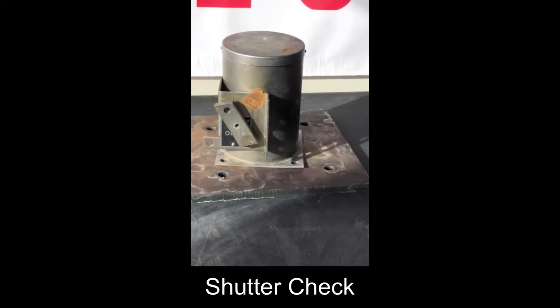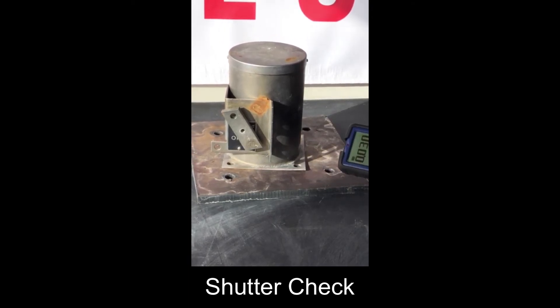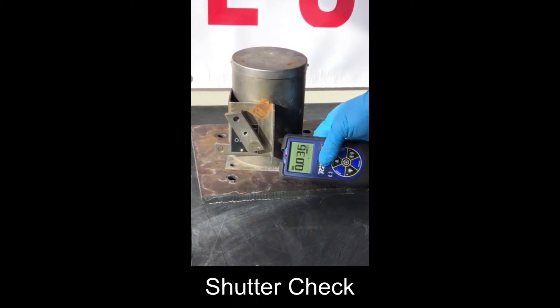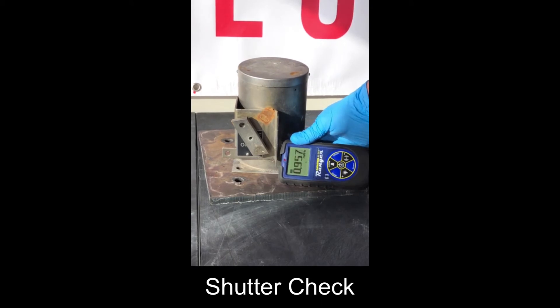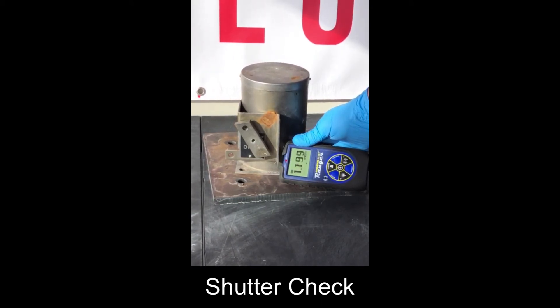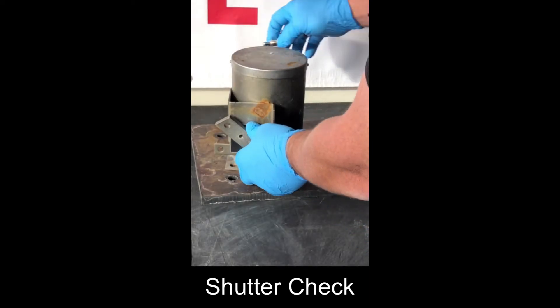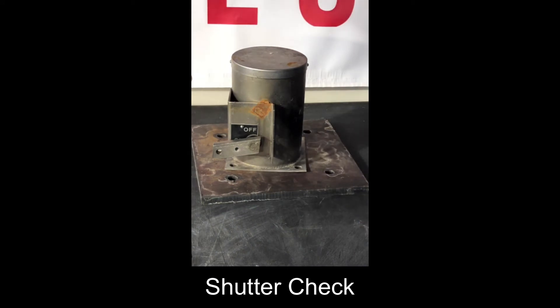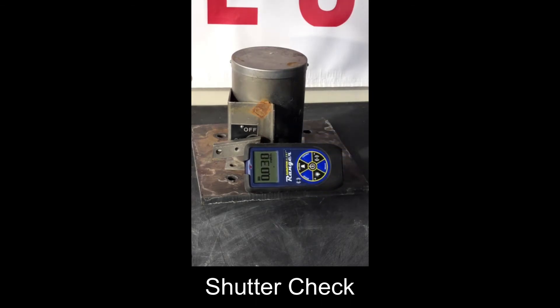Next we will perform the shutter check. We take our survey meter and approach the gauge — the gauge should be in the on position. We take our survey meter and check the dose rate at the base of the gauge. Typically this dose rate is going to be less than 5 mR/hr with the shutter open. Next we will turn the shutter off by rotating the shutter shaft to the off position, then take another reading at the base of the gauge and we'll see that it's closer to background — not necessarily background, but closer. This way we can be assured that the shutter mechanism inside is working properly.